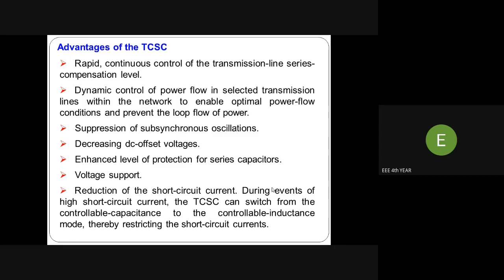The TCSC can switch from controllable capacitance to controllable inductance. Under short circuit conditions, the TCSC can immediately switch from controllable capacitance to controllable inductance mode, thereby restricting the short circuit currents.